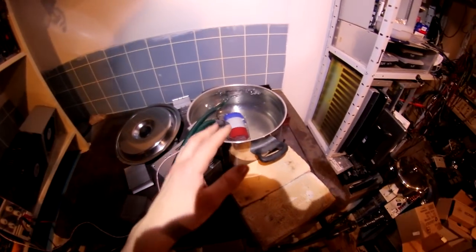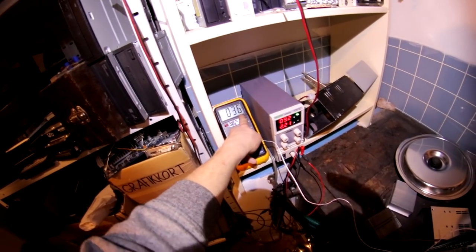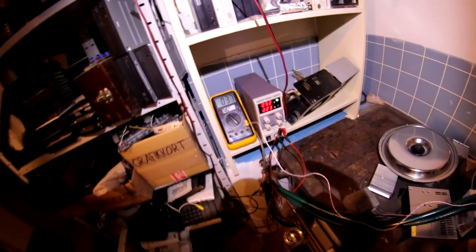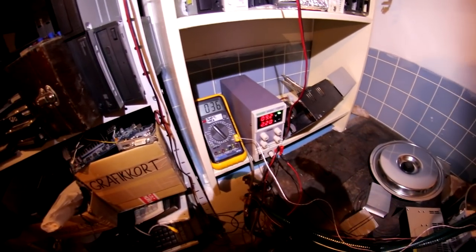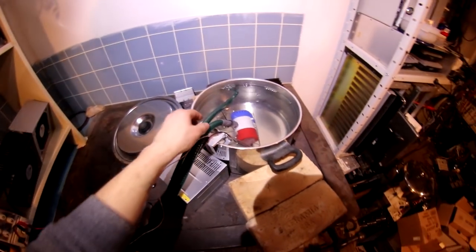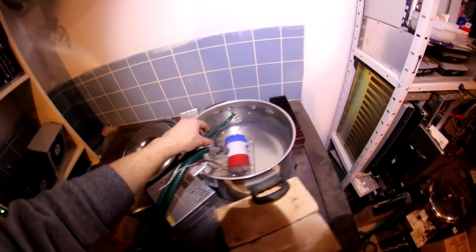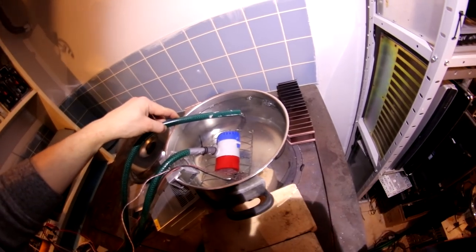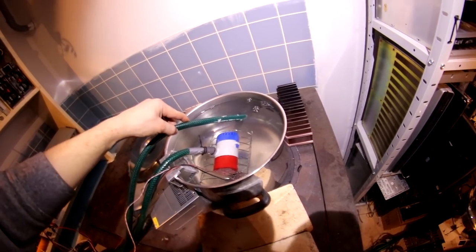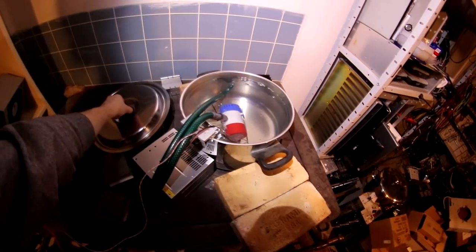We are able to run the pump and keep the water at a tasty 36C right now, and that's circulating up to the radiator upstairs. If I stick the probe into the outlet, we have about 30C coming back. So we're dropping 6C across the system and we don't have a lot of flow — it's coughing up air since the radiator is leaking.